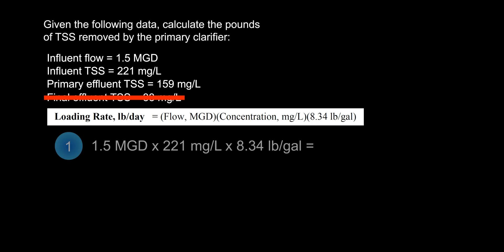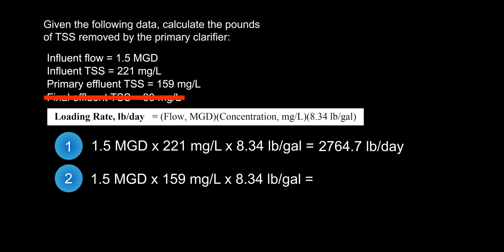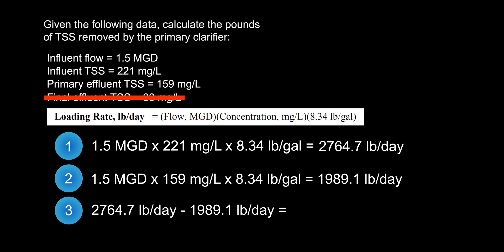For the first part of our answer, we're going to solve for pounds per day of influent TSS: 1.5 MGD times 221 mg/L times 8.34 pounds per gallon equals 2,764.7 pounds per day. For the second part, we figure out the pounds per day of primary effluent TSS: 1.5 MGD times 159 mg/L times 8.34 pounds per gallon equals 1,989.1 pounds per day. Lastly, we subtract our second answer from the first: 2,764.7 minus 1,989.1 pounds per day.